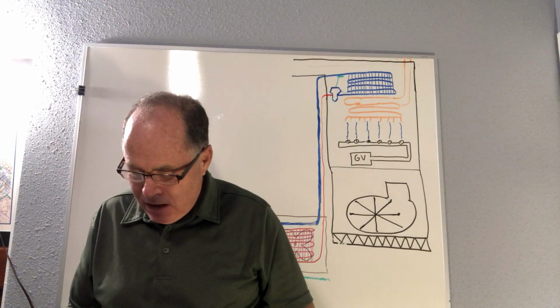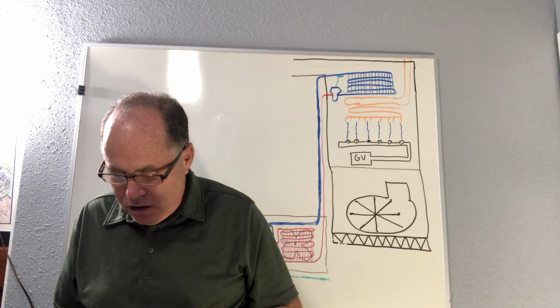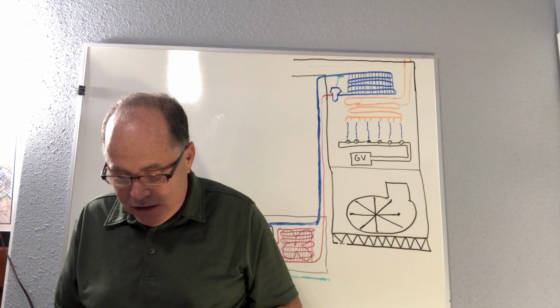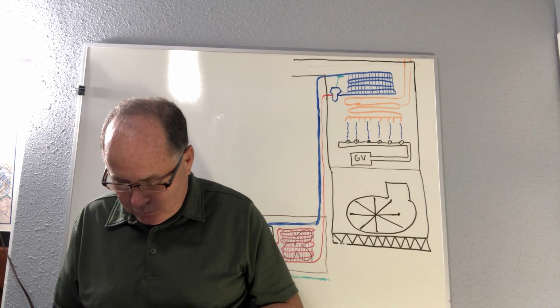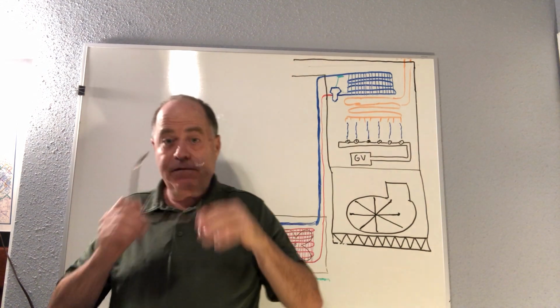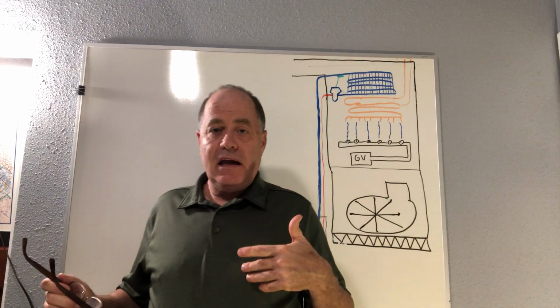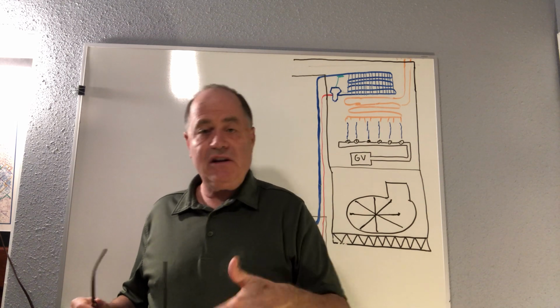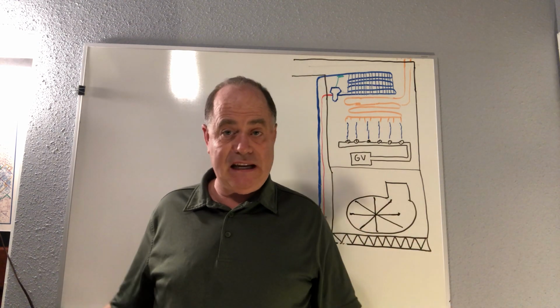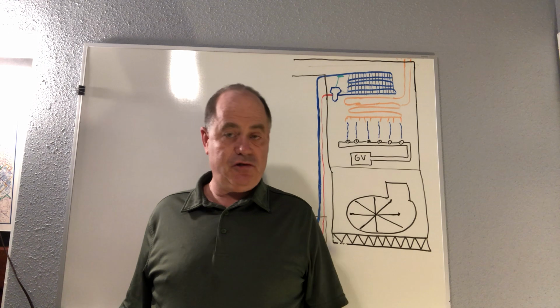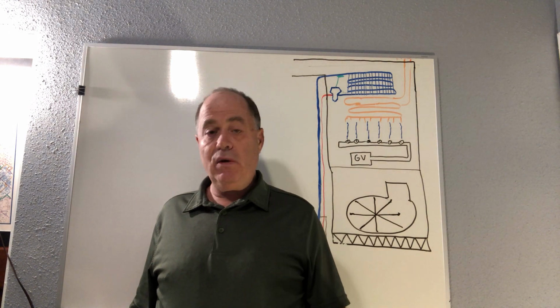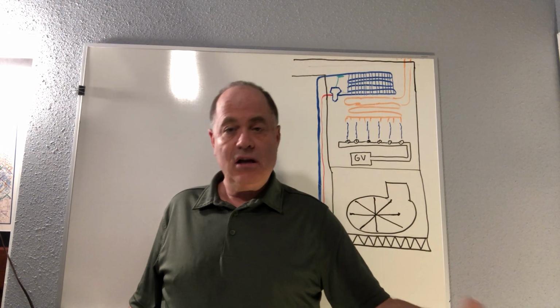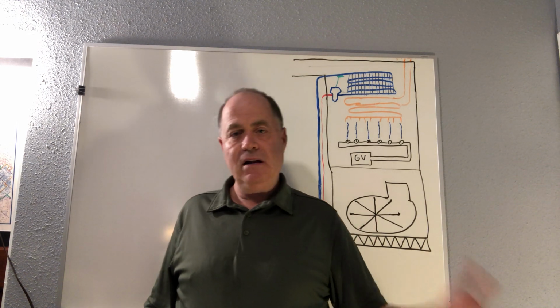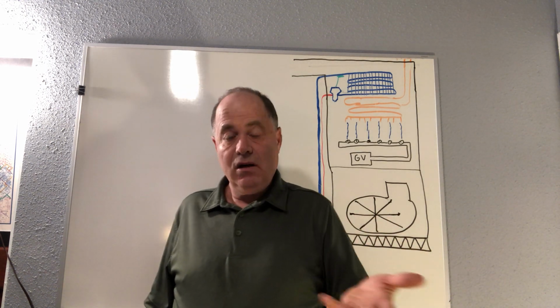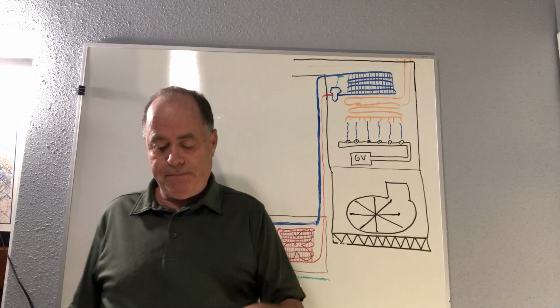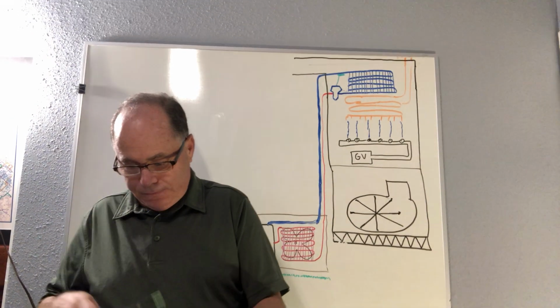It should be saying the fan should operate. It should be that you can run the fan without the duct heater. But here it's saying, like, whenever you go to run the fan just for ventilation, you need to have the duct heater on, which is wrong. It should be that whenever the electric heater is on, you've got to have the fan running, but not the other way around. Otherwise, sometimes we just need ventilation without heat. Okay? All right.